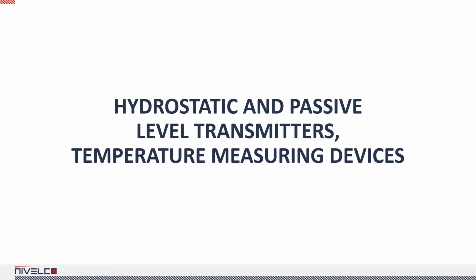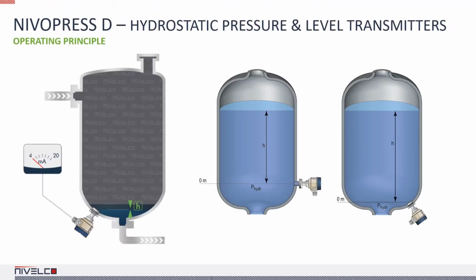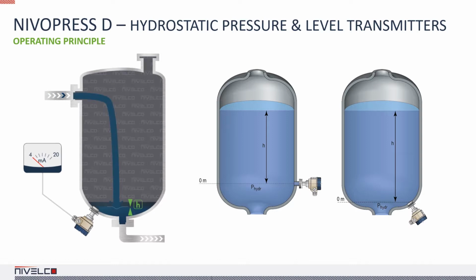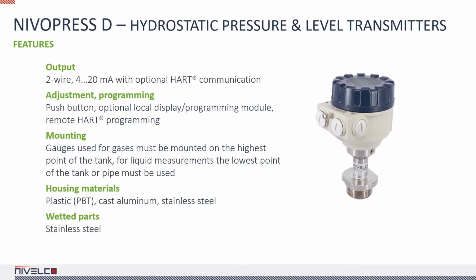Today we're discussing various level and temperature transmitters. NIVOPRESS D hydrostatic level and pressure transmitters operate in two-wire systems and convert relative and absolute pressure into 4 to 20 milliamp signals. The piezoresistive sensor measures the hydrostatic pressure and compensates for the atmospheric pressure. In homogeneous liquids, the hydrostatic pressure is measured at the bottom of the tank. It's proportional to the height of the liquid column. Devices used for gases must be mounted at the highest point of the tank.